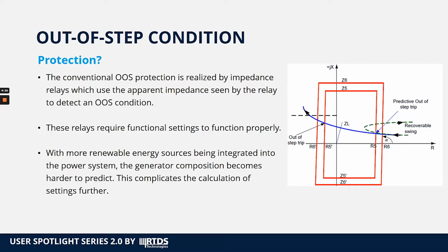With more renewable energy sources being integrated into the power system, the generator composition becomes harder to predict, and this in turn complicates the calculation of protection settings for the impedance-based out-of-step protections even further. So it becomes difficult to assess which type of generator composition should be used for the settings calculation and what actually to set as the values for the protection.